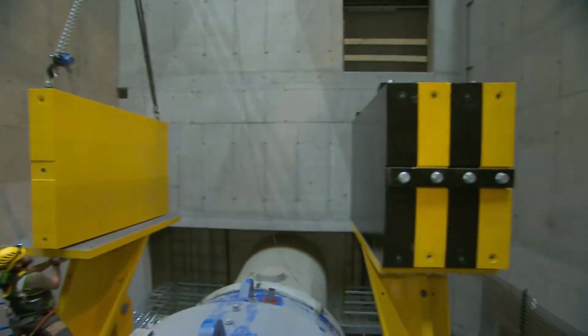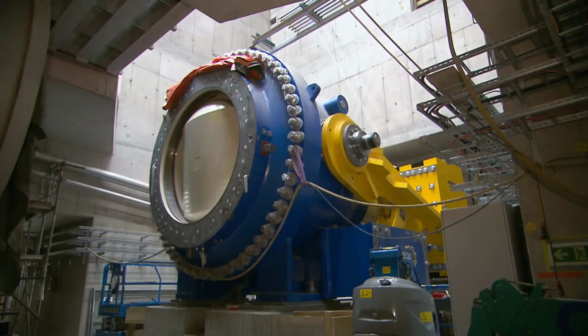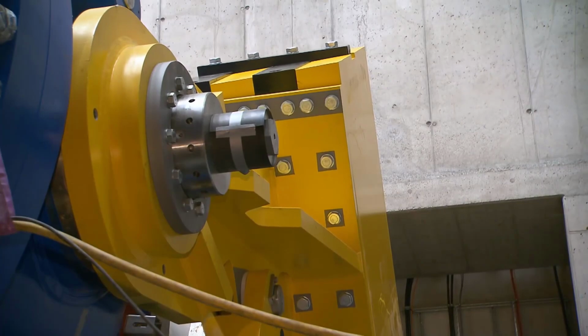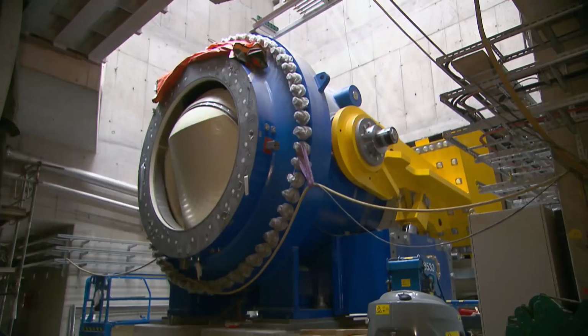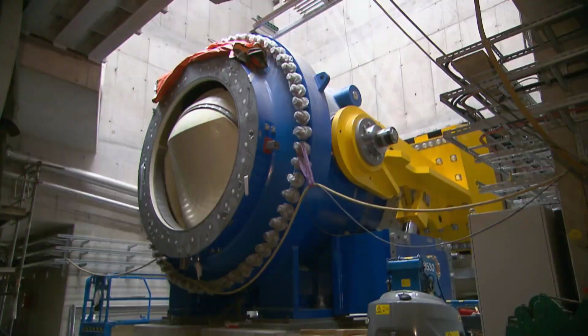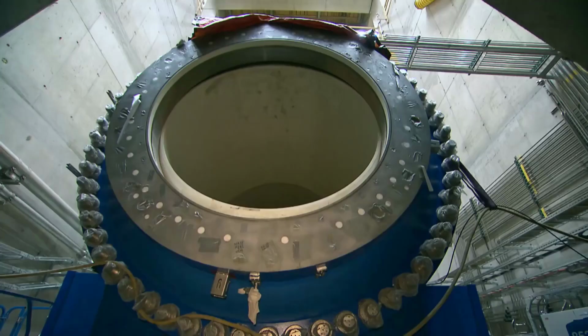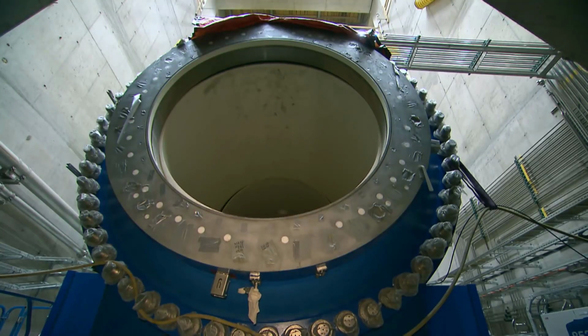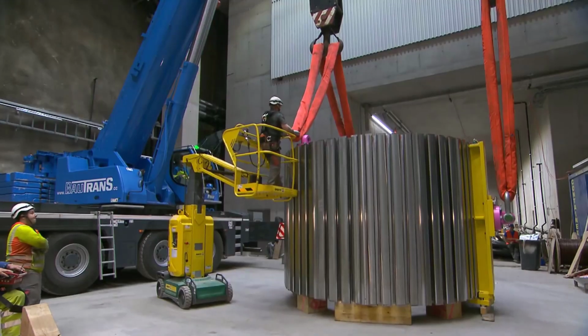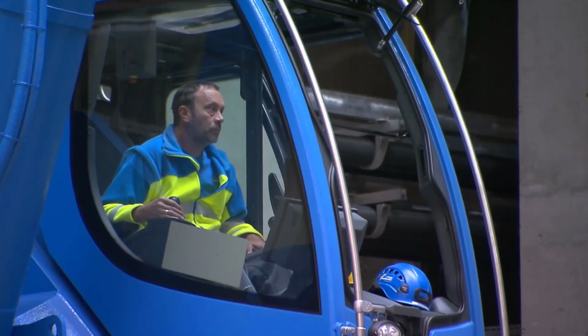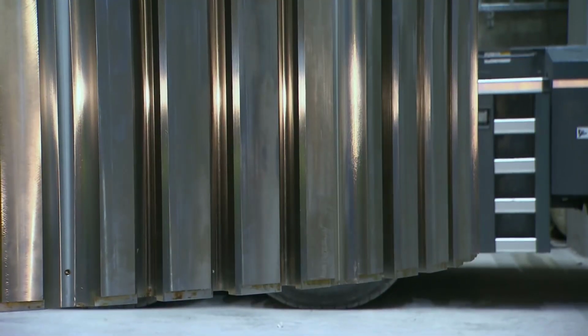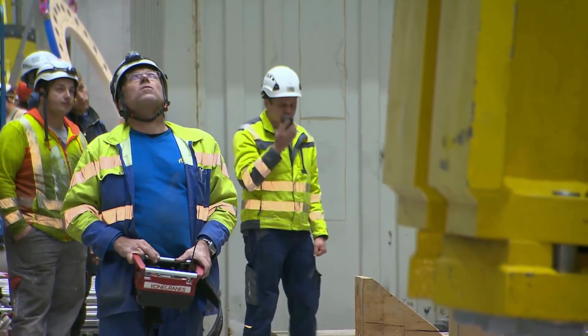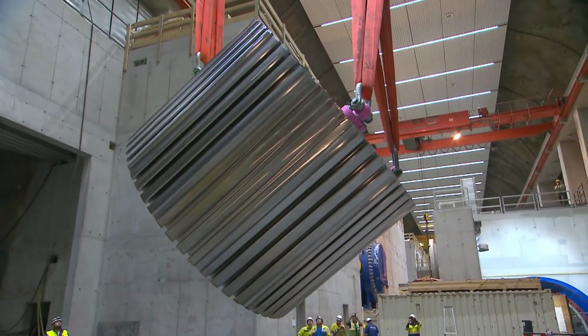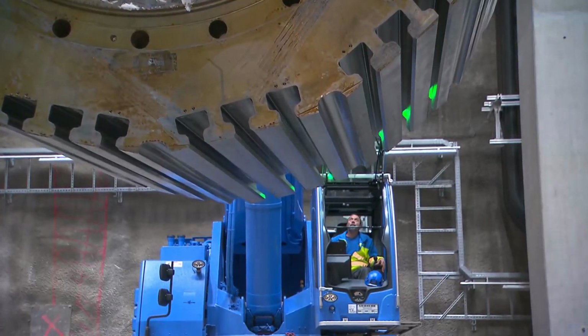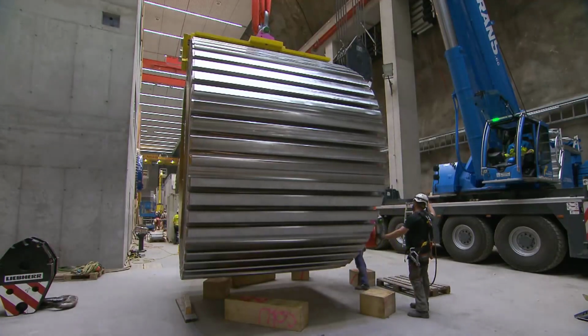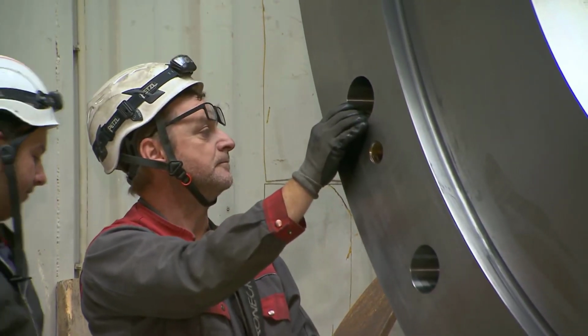First, the rotor central body must be rotated using a telehandler and the hall crane. The rotor central body must not touch the ground during this process to prevent any damage, requiring absolute precision from both crane operators. The 2 shaft pieces, manufactured in Italy, are first screwed to the rotor central body. Only then can the entire part be lifted into the lower stator half. Both haul cranes are needed for transport, as the weight of the entire rotor central body exceeds the maximum load of a single crane, which is 180 tons.